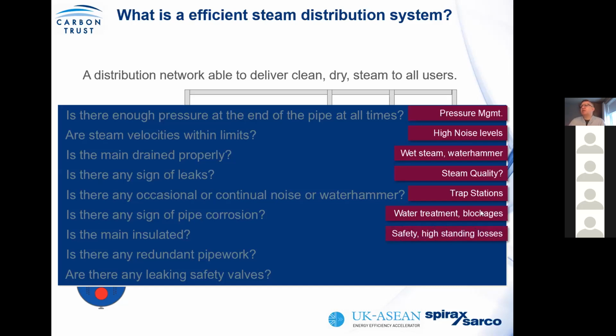Again, we talk about some things, insulation. Just because insulation was installed 20 years ago doesn't mean it's best in class now. For exterior applications, is it cladded? Is it protected from water ingress? Is it sagging? Is it wet? Wet insulation is worse than no insulation. So in other words, it should be checked on a continuous basis. And with redundant pipework, you should look at whether there is unnecessary heat loss where a production area is not in use anymore. Isolate it. If you don't have an isolation, through a shutdown, put in an isolation valve to allow you to take down the header.